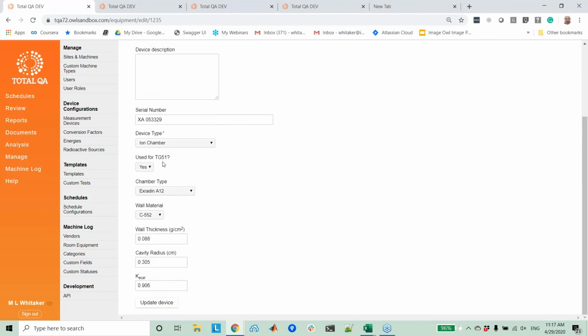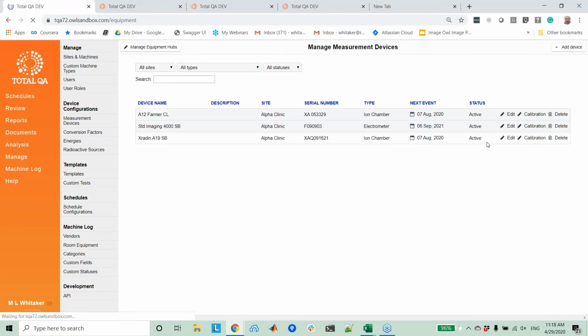When you're setting up the chamber, you pick the chamber type from a standard list. It will then automatically load up the default factors for that, from the manufacturer's published information, and those are editable. We are in the process of updating some of these ion chamber lists, and I'll speak a little more about this at the end. What we occasionally run into is a manufacturer having a different model name, but the relevant factors are just about the same. So that's just setting that up.